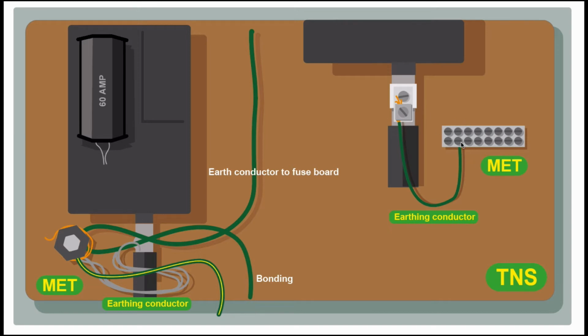Don't be dealing with that at all. I'm happy to deal with this section here, this end here, because we can unscrew from the main earthing terminal and we can test from there. But I never touch these connections here. If there's any issues with this here, the clamp, call the DNO to come and deal with that, because you do not want to be causing any short on this cable. That's just going to cause mayhem.